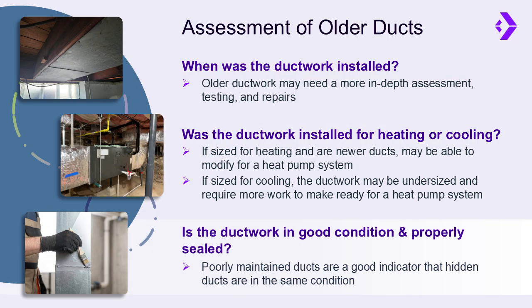Finally, assess the condition of the ductwork. Is it in good shape and properly sealed and insulated? You want to install a heat pump that can provide the right amount of heating and cooling to the building, so you don't want to undermine performance by losing a large portion of that energy into attics, crawl spaces, or basements through leaks and bad duct insulation. These questions can help guide your assessment and ultimately inform your decision to retrofit the duct system or not.